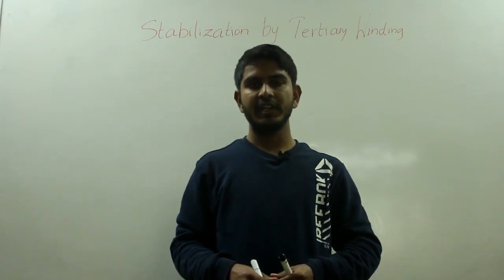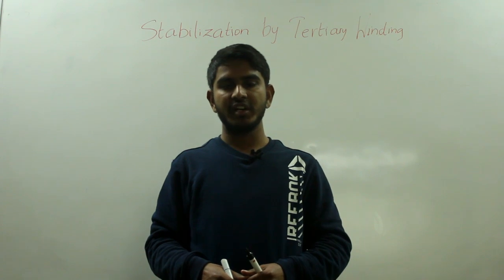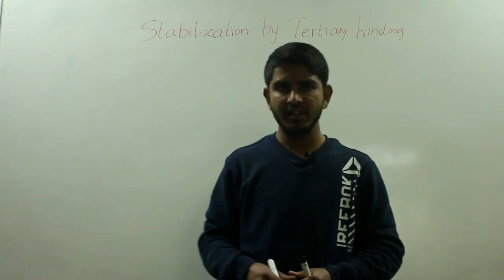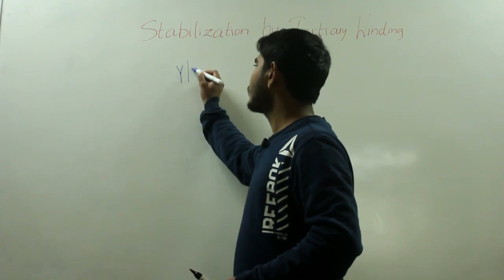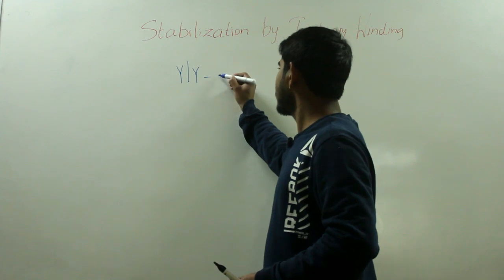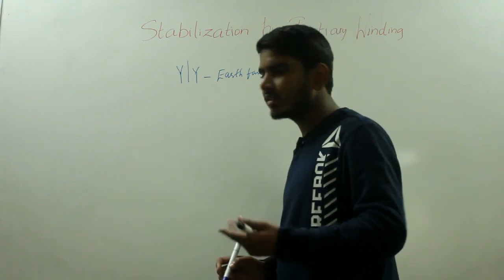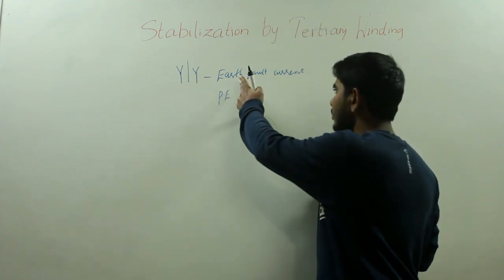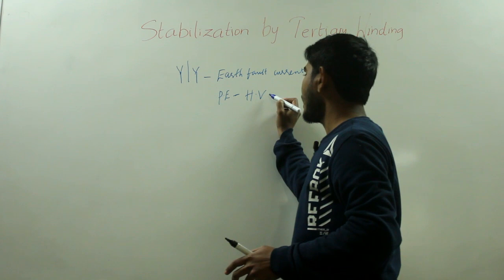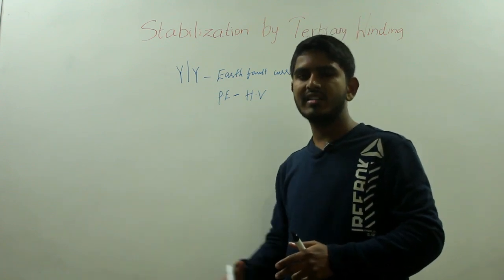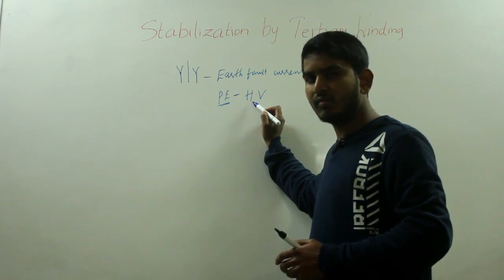Hello friends. In this video, let us discuss stabilization by tertiary winding. In our last video on the three-winding transformer, we discussed the several uses of having a tertiary winding. One important advantage is that in a star-star connected transformer, the tertiary winding allows sufficient earth fault current to flow for the operation of protective equipment, to suppress harmonic voltages, and to limit voltage unbalancing when the main load is unsymmetrical.